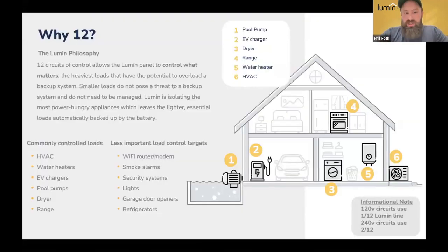Probably the question we get most often is why we chose 12 circuits as opposed to, say, 40 for the standard service panel. We're trying to really target those heavy loads. The commonly controlled loads we attach Lumin to are your HVAC system, water heaters, EV chargers, pool pumps, dryers, and potentially electric ranges. Obviously gas is not so much of a concern.